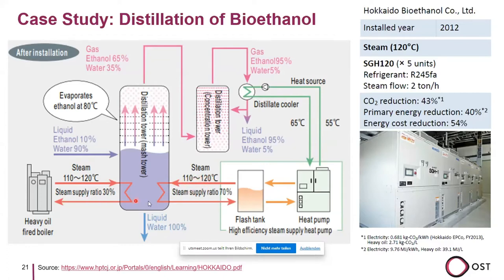And this way they can split the steam supply, with 70% going to the heat pump. Before it was 100% by an oil-fired boiler. So they can save a substantial amount of oil, reduce the CO2 emissions, and also reduce energy costs. What they have is a system of heat pumps in parallel, I think five units, to increase the heating capacity.